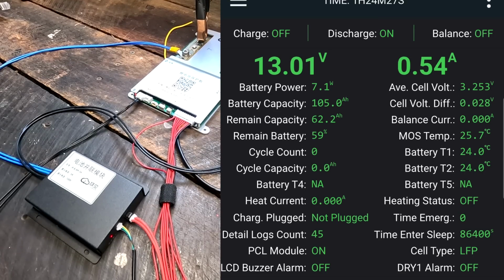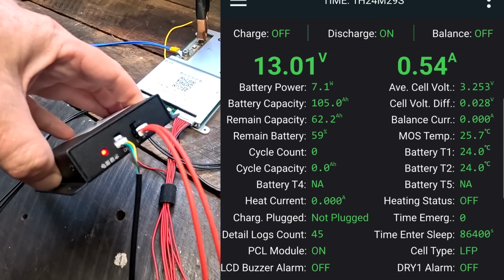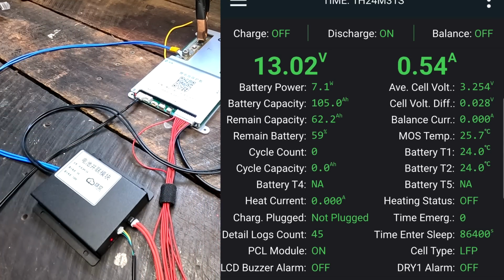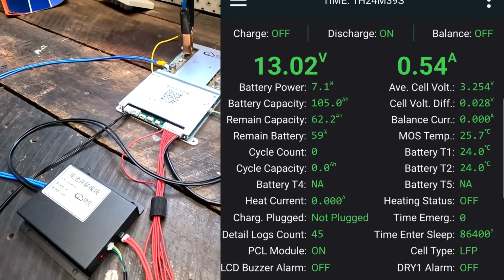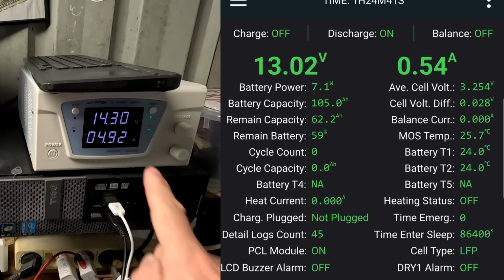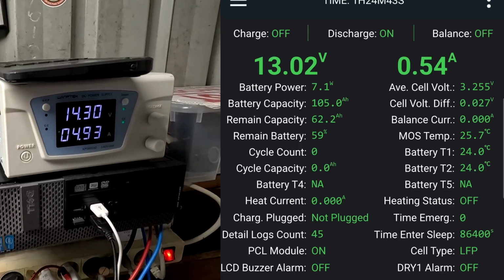Okay, it's now 20 minutes later and the current limiter is still active. So the BMS does not turn off the current limiter and go back to normal charging, even though our charging current is under the set limit. You can see here the power supply still supplies 5 amps.